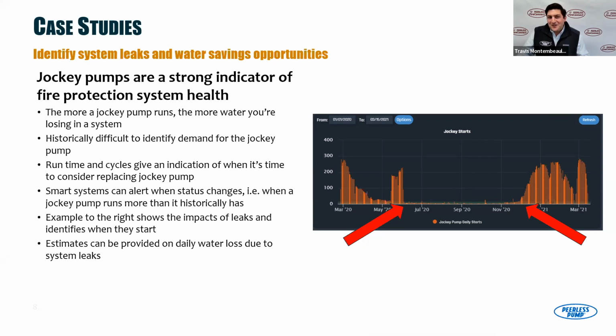We don't really look at the jockey pump unless someone's physically standing in the pump room, looking at the counter or with a stopwatch, seeing how many times it turns on in a 20-minute period. We're not really paying attention to it, so we're not necessarily knowing when issues may pop up. Being able to send a text message when your jockey's starting more than it normally does is a leading indicator that an issue is starting to crop up.